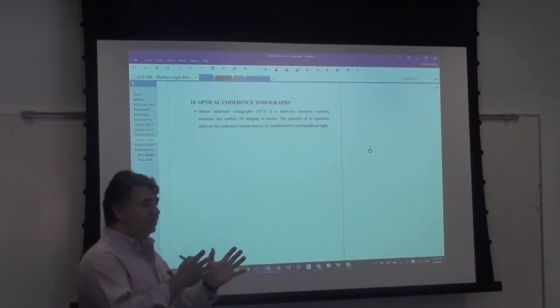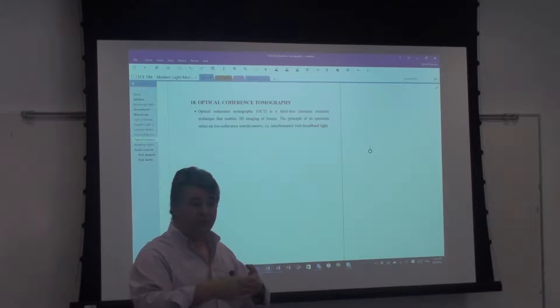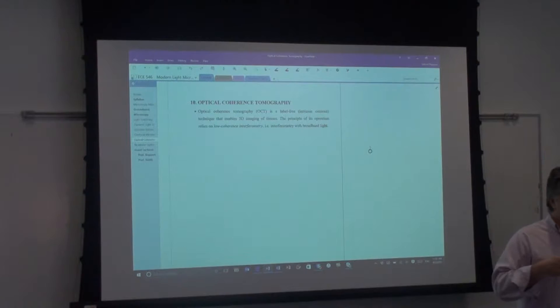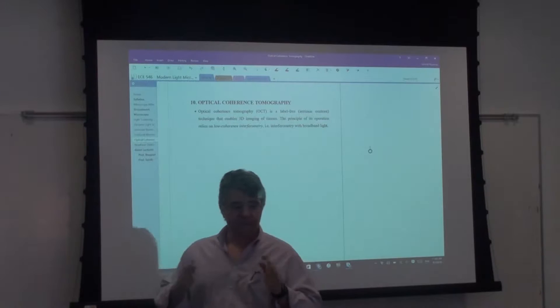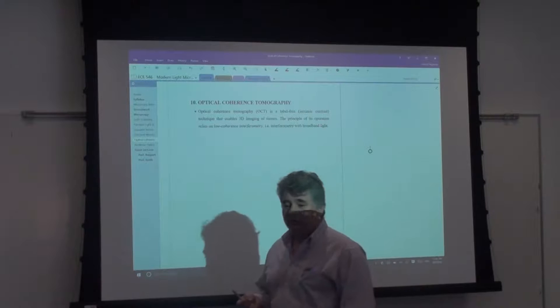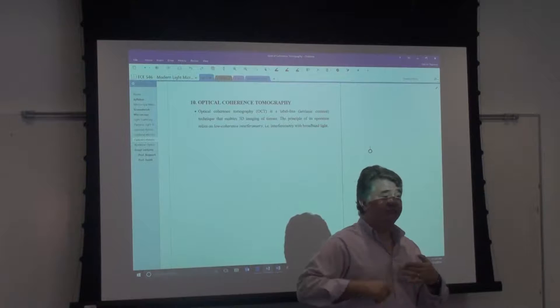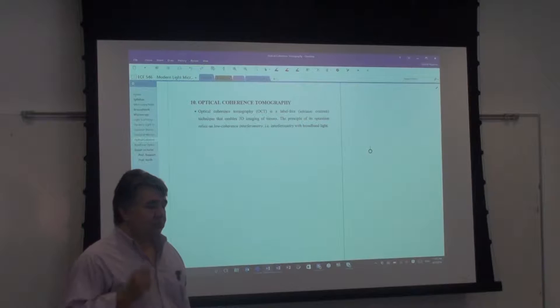Remember in a regular microscope your resolution in X and Y depends on numerical aperture — in confocal you focus light down, and the higher the resolution in X and Y, the tighter the depth of field in Z as well. This limits the depth over which you can collect information at one time. In OCT this connection is broken: the Z information comes from the coherence properties of the light — the Z resolution is given by the coherence length of the field. This means you can have a low NA illumination and still have depth sectioning, which is not true for any other microscope.